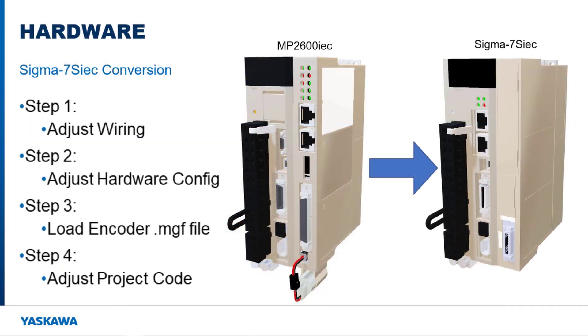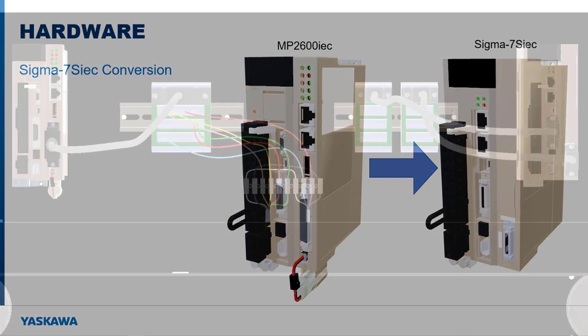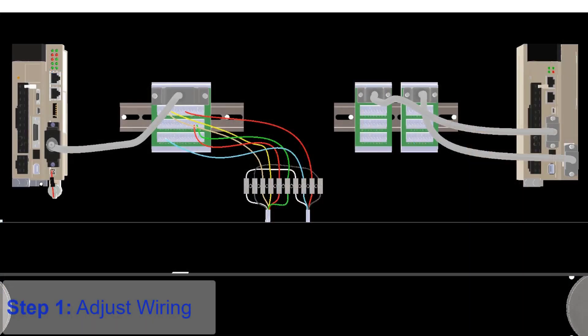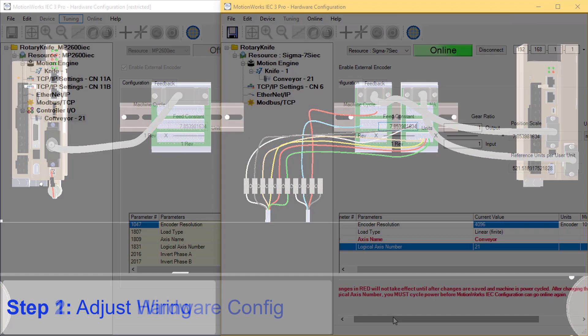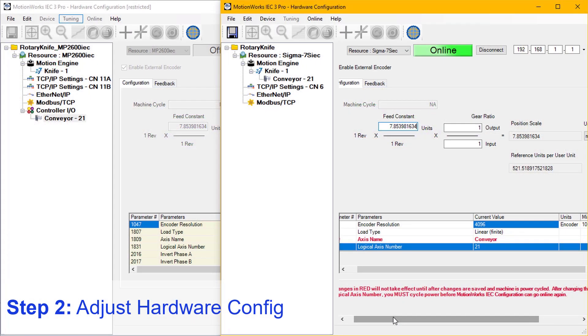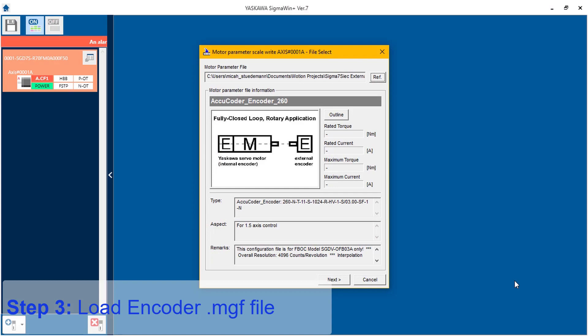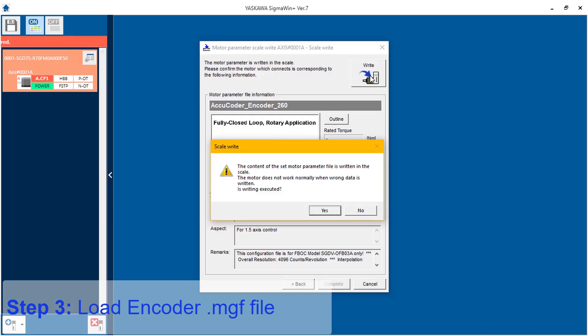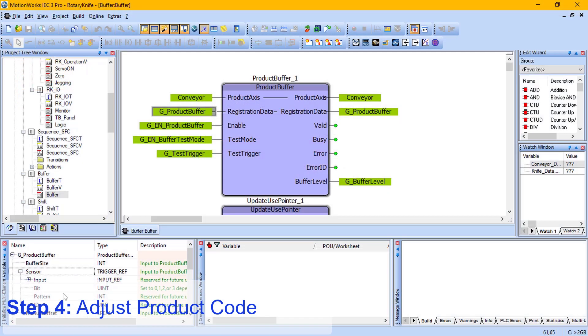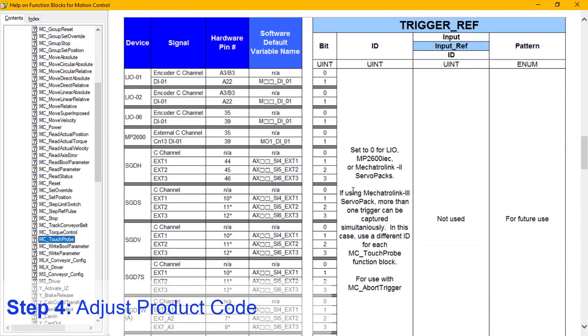There are four steps to convert from the MP2600 IEC to the Sigma-7S IEC. Step 1: the I/O wiring needs to be adjusted. Step 2: hardware configuration needs to be modified for the Sigma-7S IEC. Step 3: the encoder manufacturing file needs to be loaded into the feedback option card. Step 4: the MotionWorks IEC project code needs to be modified for I/O differences.